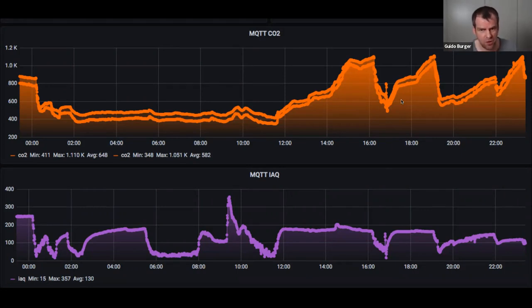And the other sensor, which is a non-optical sensor, a MEMS sensor, is looking at VOC, at organic substances like alcohol or also from the breathing. This is what we measure with the other sensor. And this is a VOC sensor? VOC stands for volatile organic compounds. Yeah. The VOC sensor is also capable, with some mathematics, of calculating an equivalent CO2. So if you see a small e in front of the sensor specification talking about CO2, then this means equivalent CO2. This is a calculated CO2 value.